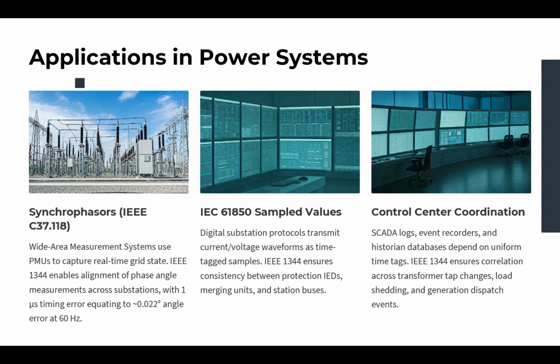Another aspect in the power system is the SCADA system, which is supervisory control and data acquisition. SCADA manages the grid operation by collecting the data throughout the system and making a decision on the suitable action for those measured data. Each of those data points could be a voltage level, a breaker status, or a tap changer position. They all should be time tagged so we can have an accurate interpretation. All the event records and sequence of event logs should be available for post-disturbance or forensic analysis.